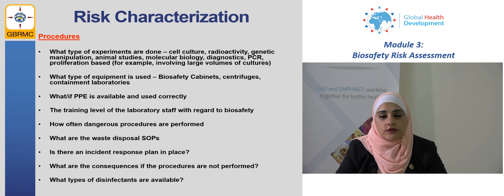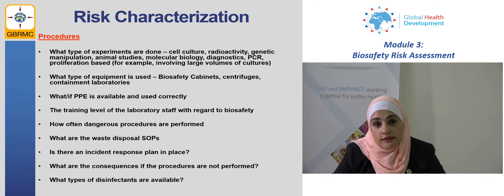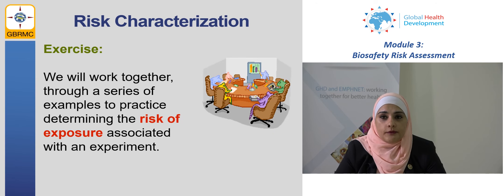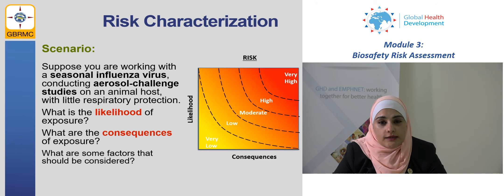Regarding procedures, we need to gather information about the types of procedures performed — for example, PCR, bacterial culture, antibiotic testing, DNA sequencing, or other biochemical testing. We need to determine whether radioactive or carcinogenic materials are used. We also need information about the equipment, such as autoclave, centrifuge, or biosafety cabinets, and the possible risks of each. Additionally, we need information about the training level of employees, dangerous procedures and their consequences, and waste management and decontamination processes.